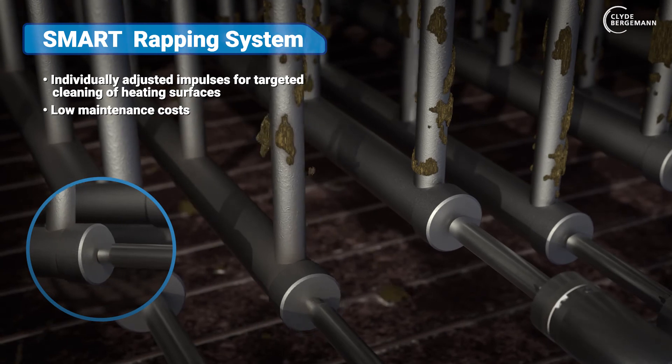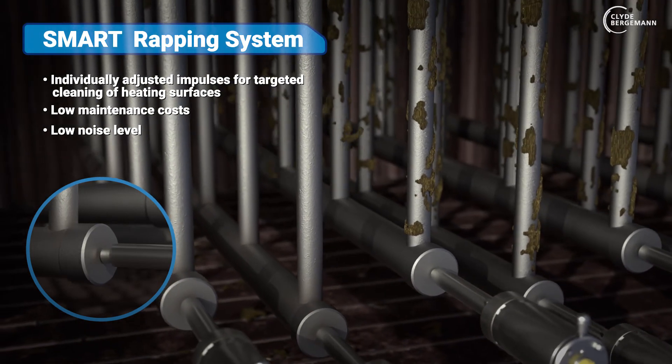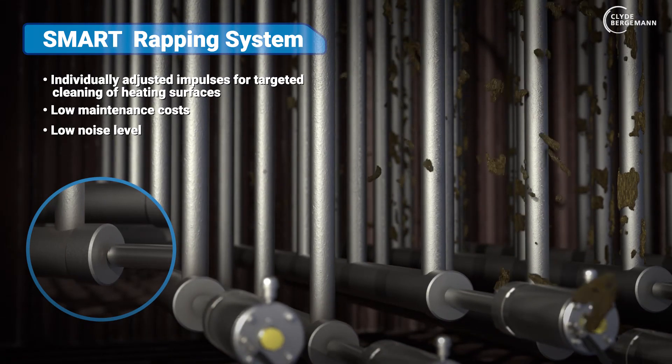The Smart Rapping System is a specific cleaning option for horizontal convection areas with suspended heating surfaces, which are brought to vibrations by controlled impulses. This causes the combustion residues to fall off. The magnitude of the impulses can be individually adjusted for targeted cleaning.